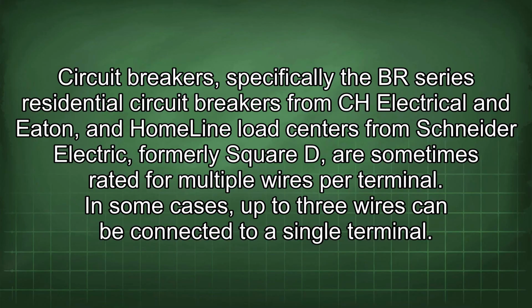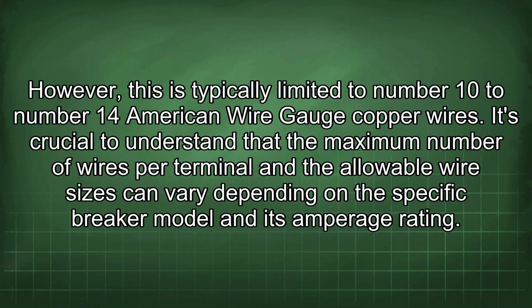Circuit breakers, specifically the BR series residential circuit breakers from CH Electrical and Eaton, and Homeline load centers from Schneider Electric, formerly Square D, are sometimes rated for multiple wires per terminal. In some cases, up to 3 wires can be connected to a single terminal. However, this is typically limited to number 10 to number 14 American wire gauge copper wires.